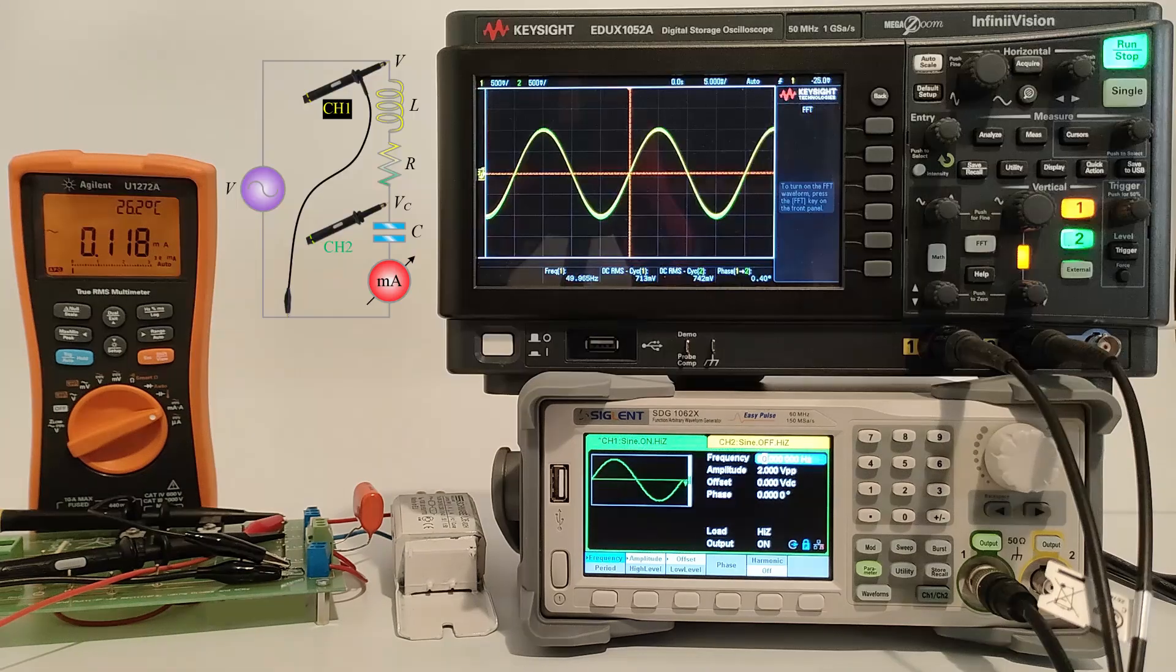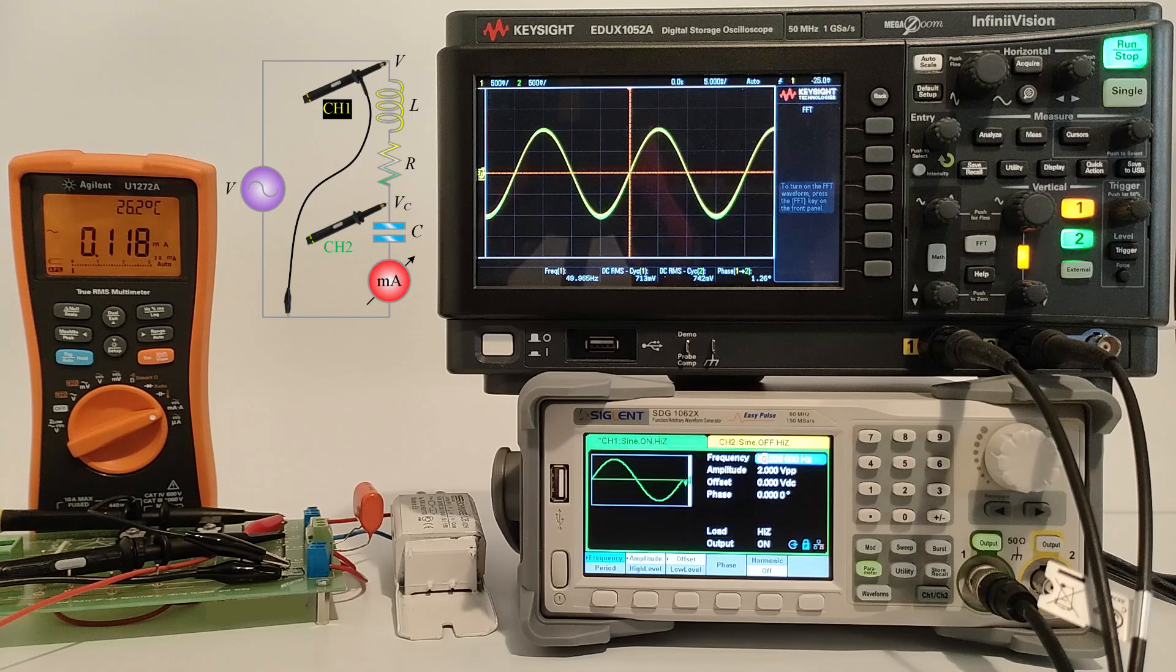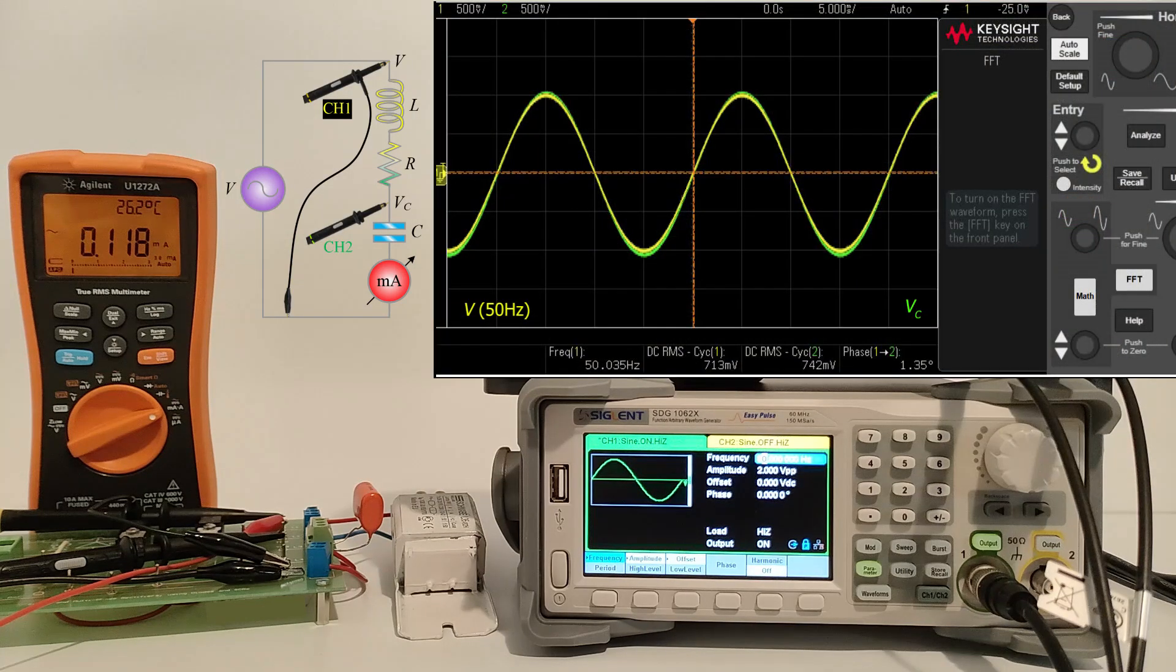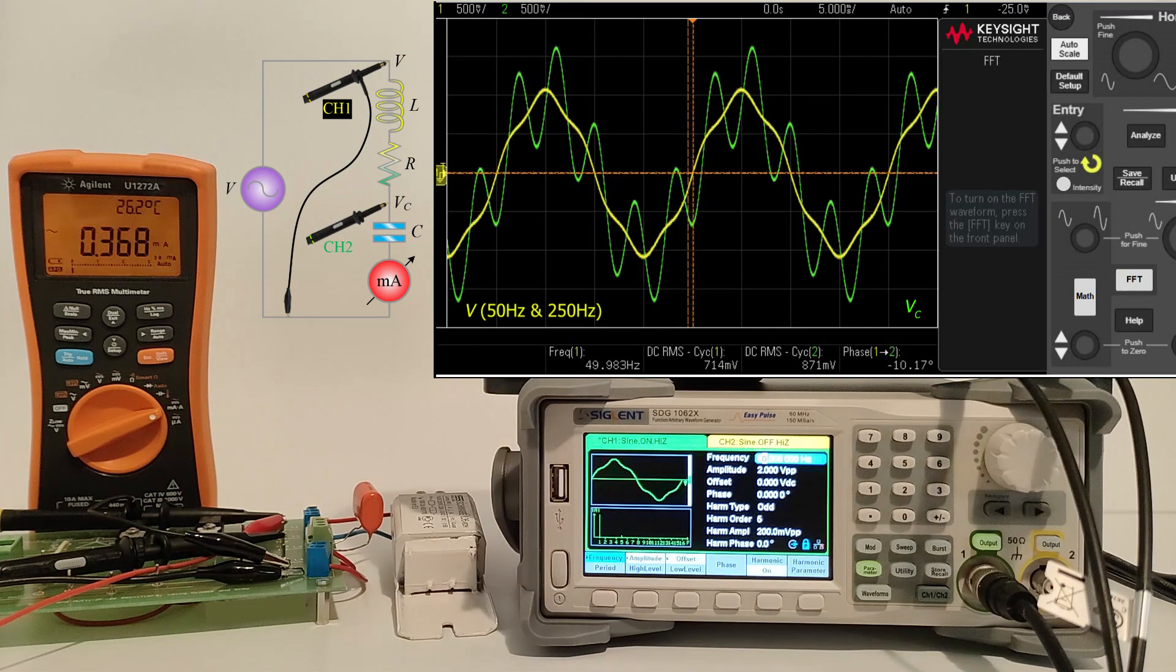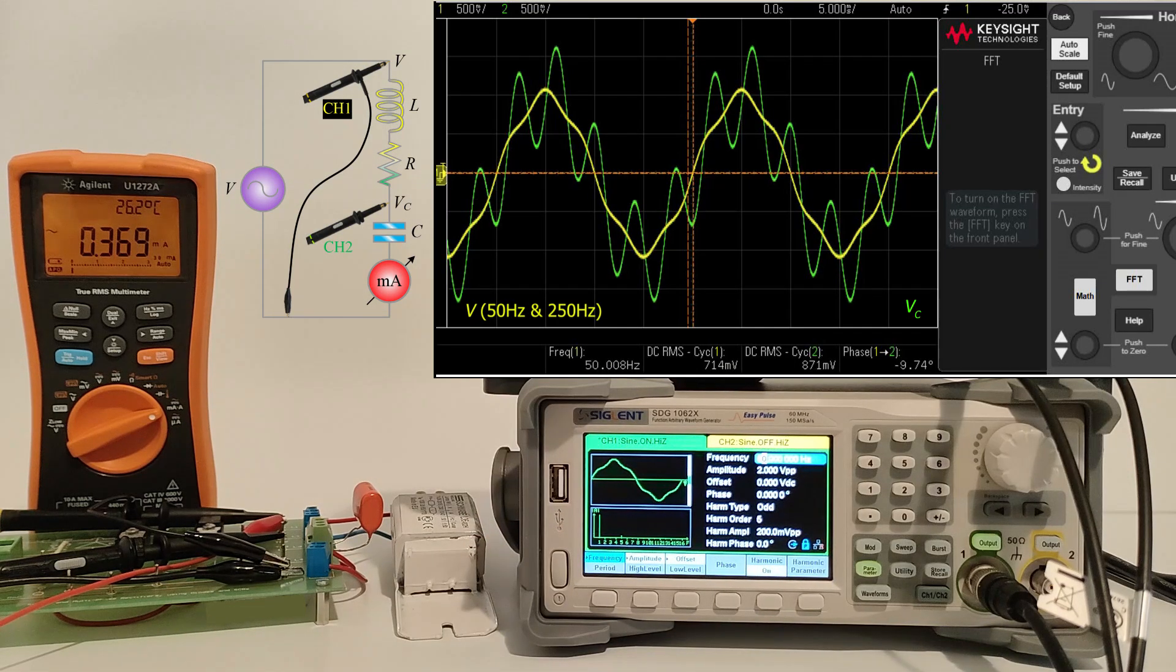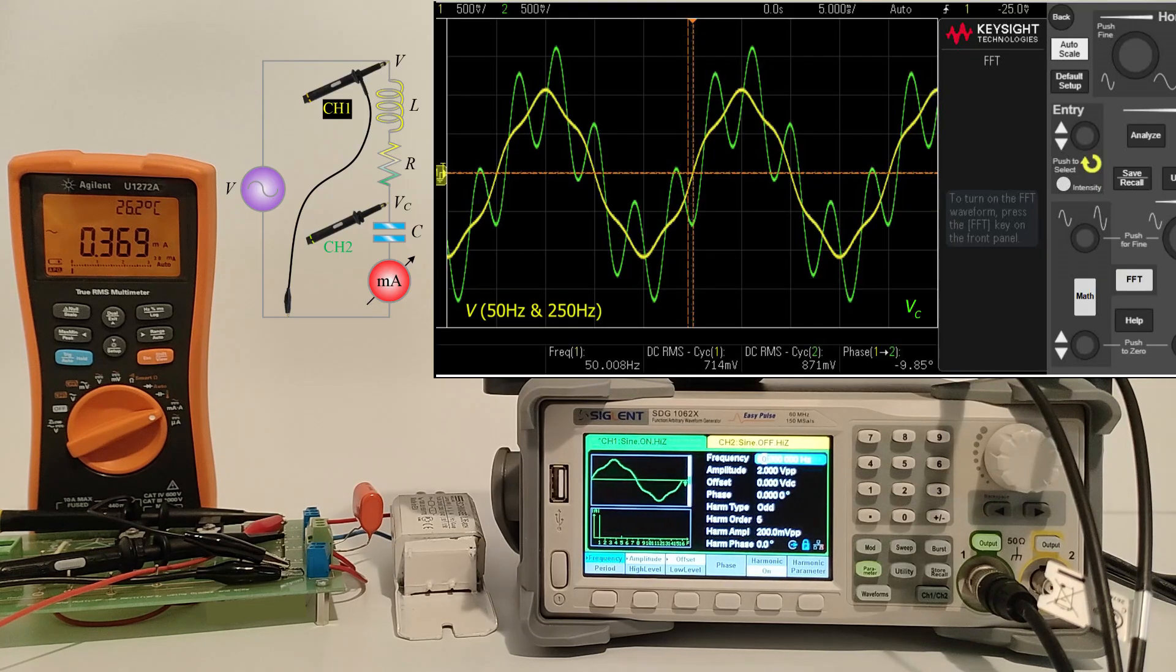Resonance is essential at telecommunication receivers but is undesirable on the grid. In particular, the distortion of the 50 hertz sinusoidal voltage, manifested by the small fifth harmonic at 250 hertz, causes due to the resonance in it the shown capacitor voltage.